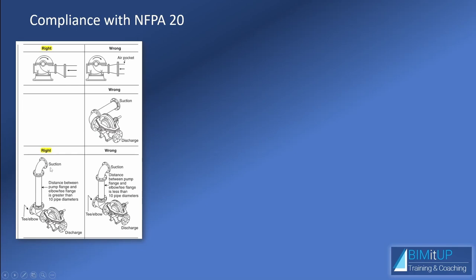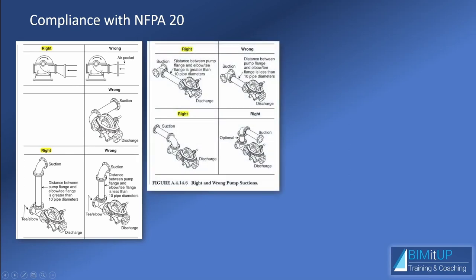You can, however, have that turn on a vertical plane. So this would be okay as long as you have 10 pipe diameters of length at the suction. So this would be a wrong installation because this is too short. It's less than 10 pipe diameters. Again, that's that horizontal turn. You don't want to have it too close. So if you will have a horizontal turn, whether it's an elbow or a T, it has to happen at least 10 pipe diameters of developed length before the suction of the pump.